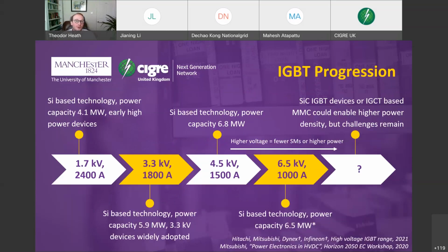So I mentioned some areas for improvement in submodules for VSC HVDC converters. One of them is always power density. While VSC HVDC is a fantastic groundbreaking technology, it's still limited in power transfer capability compared to LCC, which offers much higher power levels, as we saw in the most recent record-breaking link, the 12 gigawatt link in China between Changji and Guquan. But to push up the power capability in VSC without significantly increasing the complexity and size of the system, unsurprisingly, we're going to need to drive forward the core power electronics.